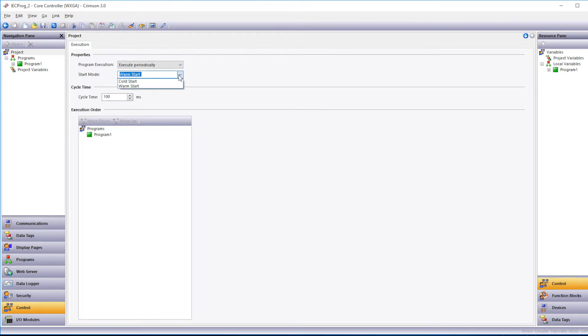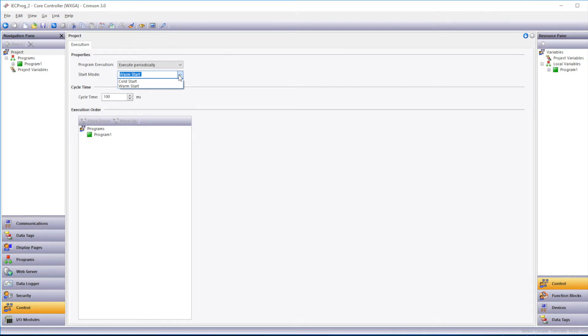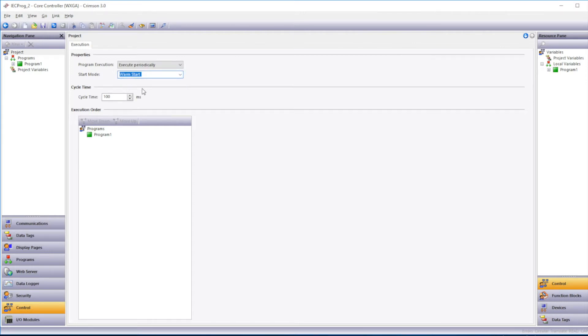The Start Mode field sets what the default values of the variables will be on a Power Cycle. So Warm will show the last value, so that will be the last known value before the controller was Power Cycled. Cold will set the variables to 0 or the default value.